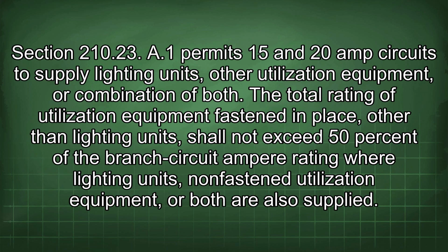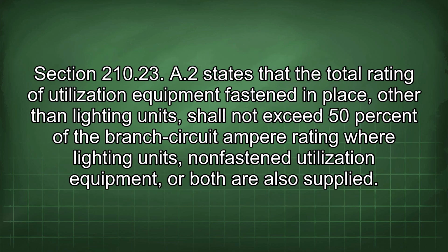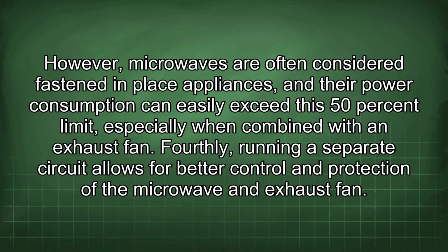Section 210.23(A)(1) permits 15 and 20 amp circuits to supply lighting units, other utilization equipment, or a combination of both. The total rating of utilization equipment fastened in place, other than lighting units, shall not exceed 50% of the branch circuit ampere rating where lighting units, non-fastened utilization equipment, or both are also supplied. Section 210.23(A)(2) states that the total rating of utilization equipment fastened in place, other than lighting units, shall not exceed 50% of the branch circuit ampere rating where lighting units, non-fastened utilization equipment, or both are also supplied. However, microwaves are often considered fastened in place appliances, and their power consumption can easily exceed this 50% limit, especially when combined with an exhaust fan.